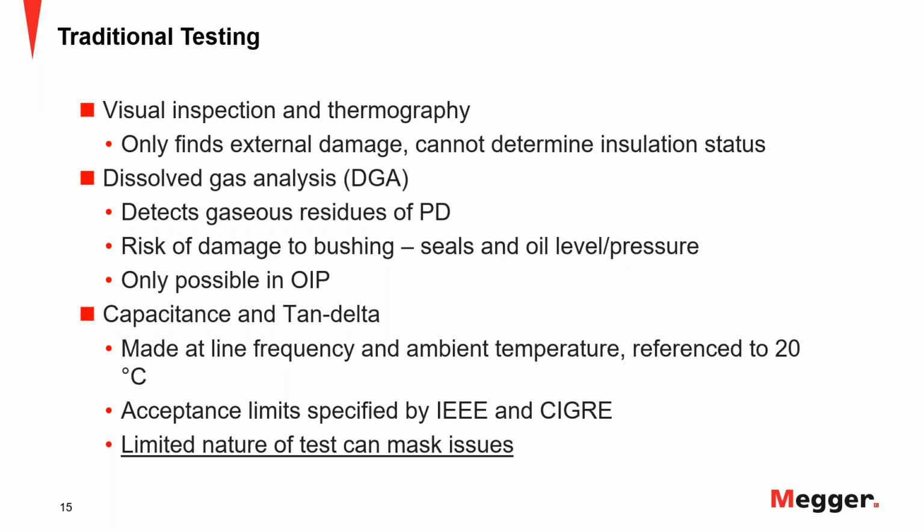Make sure that you have enough level of oil, right? Sometimes we have not noticed, and that level gauge that we have on the bushing may not show us properly the level of oil. So make sure that you take enough time to run a visual inspection of the bushings when you have the opportunity to do that before any testing.